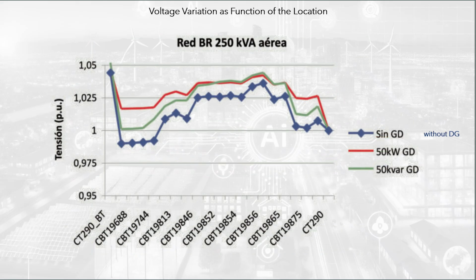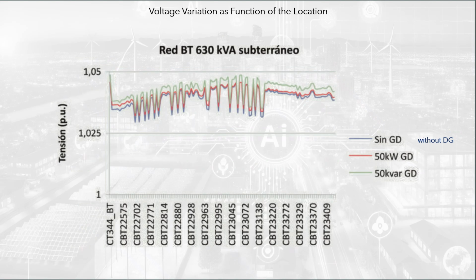Since DG is expected to occur in low voltage grids, LV, the most significant results of the impact of injection on all nodes of 50 kW and 50 kVAr are shown in the figure. In this it is observed that the impact on voltages differs according to the network analyzed. The rural overhead network has the greatest impact of active power on voltages, since the average R/X ratio is greater than 4. The low voltage network, LV, associated with the 630 kVA underground line has the least voltage variation, because it is the network with the shortest average length of the lines.